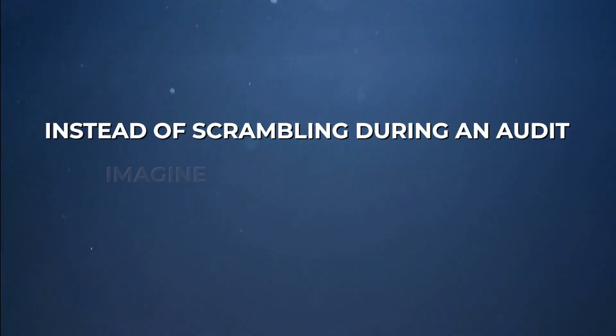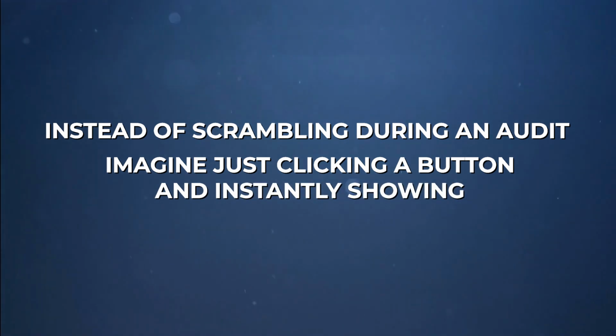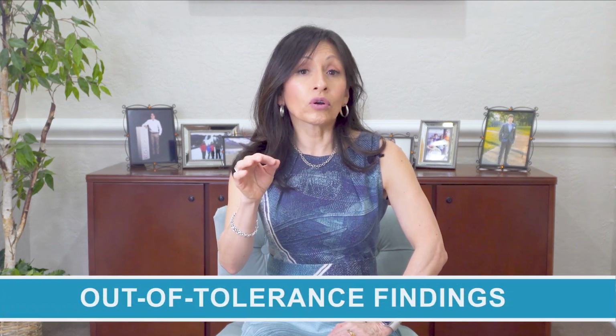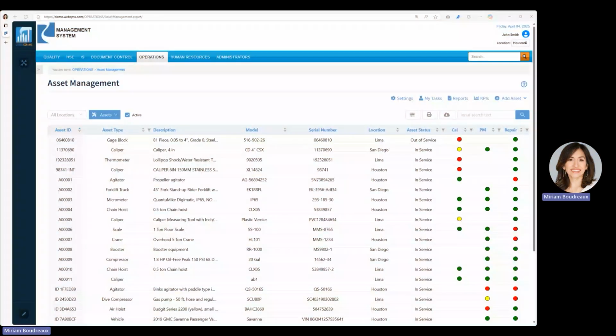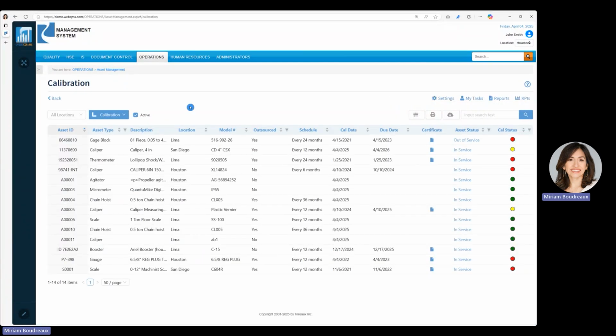Instead of scrambling during an audit, imagine just clicking a button and instantly showing every calibrated asset in your company. Proof of calibration and certificate for every tool, and corrective actions for out-of-tolerance findings. This is the Asset Management app. From here, I can filter for all assets that require calibration or verification.